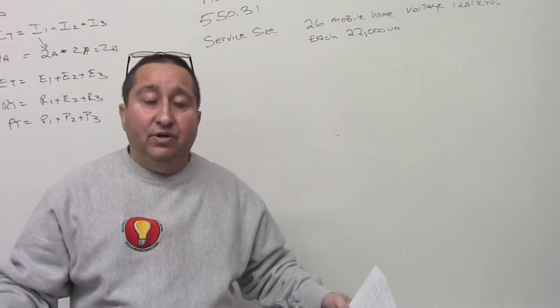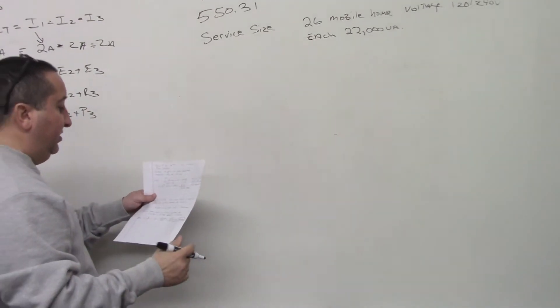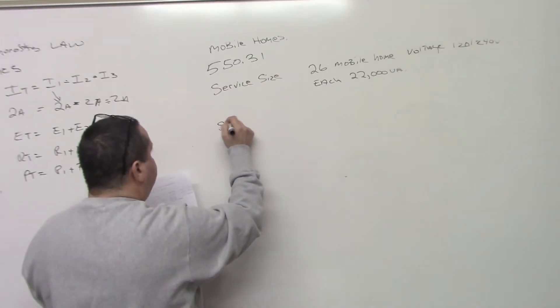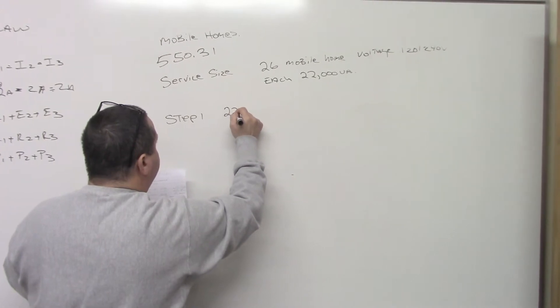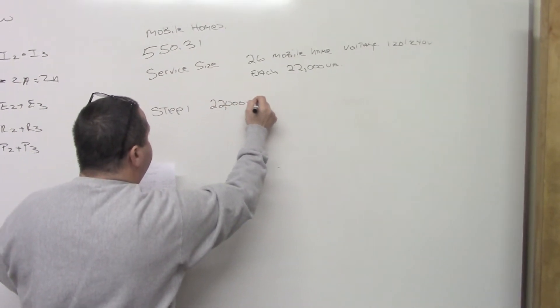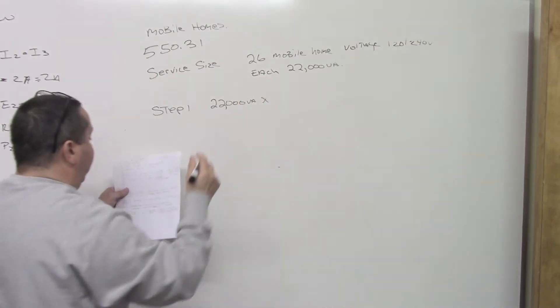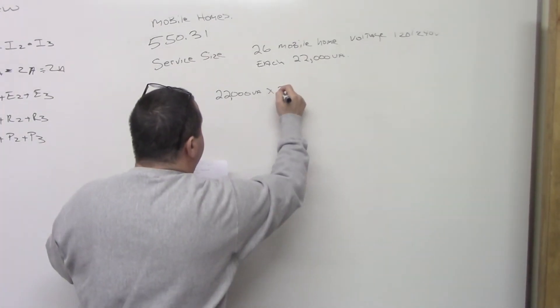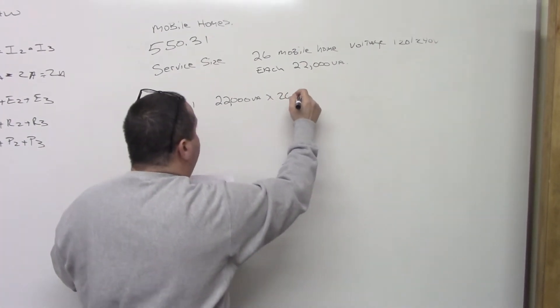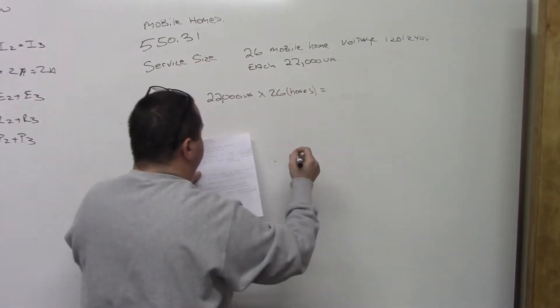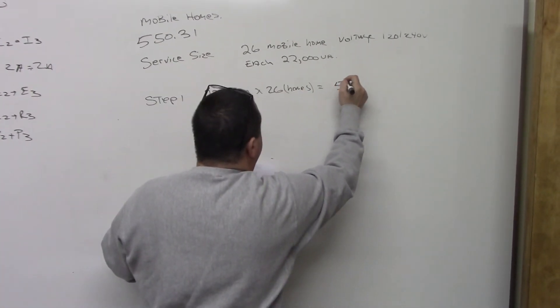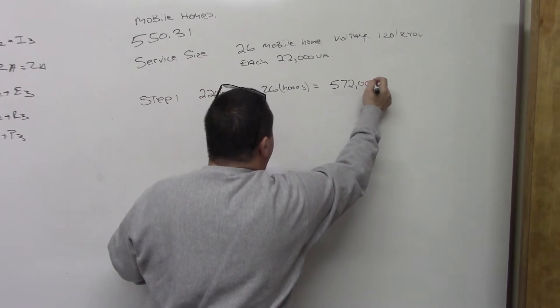So step one, what we're going to do is we're going to go 22,000 volt amps times how many mobile homes? 26. Which equals 572,000 volt amps.